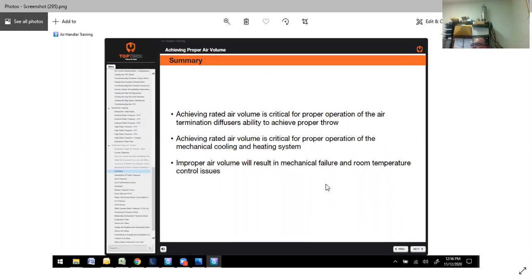Achieving rated air volume is critical for proper operation of the air terminal diffusers to basically throw the air where it needs to go. Depending on where they're located, they have to be able to throw and distribute to the whole room. It's imperative for proper operation of the mechanical heating and cooling systems. Improper air will result in mechanical failure and room temperature control problems. As you get into variable speed and inverter systems, it is super critical. You'll just open yourself up to all kinds of failures that will ultimately have to be resolved before the issues go away.